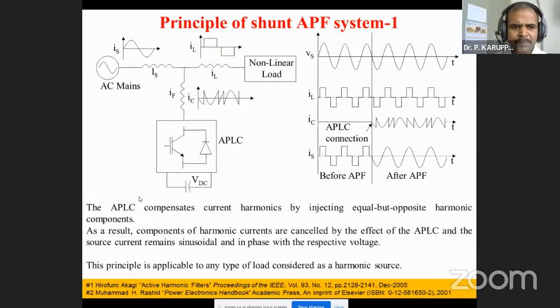The AC power is the main source, which we get from the sub transformer, and the non-linear load is connected in our home appliances or small scale industries, even big industries. So non-linear loads are connected. When we connect the non-linear load, it will generate current like this. You can see from this graph. The first is the power supply, which is fine, and the second is the load current. Here the load current becomes non-linear. Here I used a rectifier load, a diode rectifier load. Because of the diode rectifier load, you can see the 6 pulse signal, whereas we need a sinusoidal signal. From this it is easy to understand that it has harmonics; higher order harmonics are present.